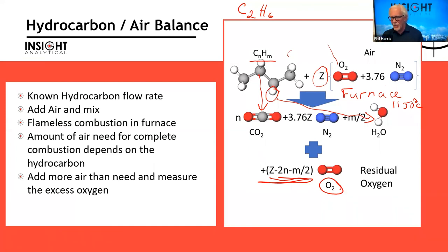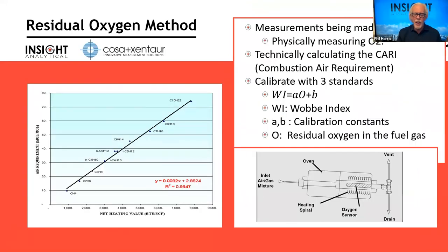So we have this flameless combustion that goes on. We've got more air than we need. We consume all of the hydrocarbons. The reason we run the furnace so hot, sorry, this is supposed to be 1,050, not 1,150. We run that furnace so hot so that we get complete combustion. And then the amount of residual oxygen that's left over gives us a measurement of the average chemical structure of the hydrocarbon stream: how many carbons it has relative to how many hydrogens it has. And that becomes important to us because we know there's a really great correlation between this and heating value. Sorry, the text is a bit small on the bottom, so I'm just going to put this down here. This is heating value down here.